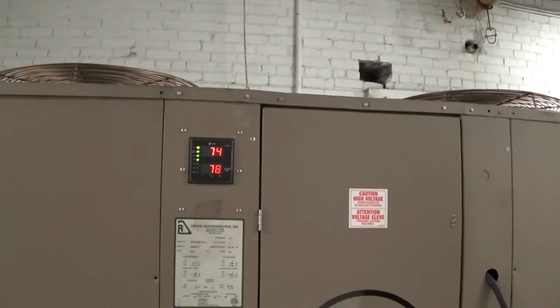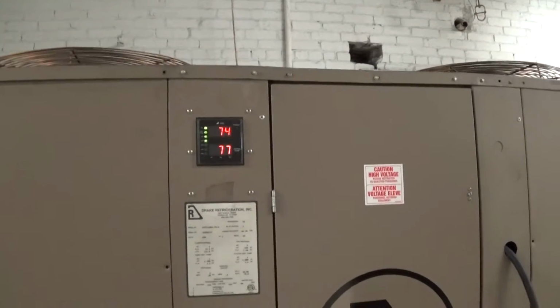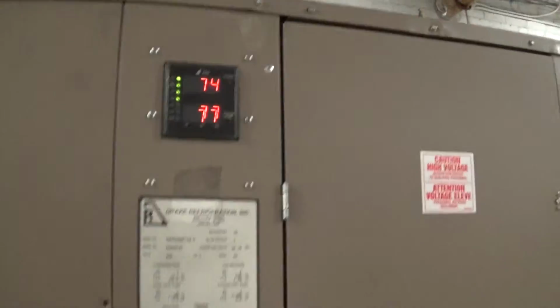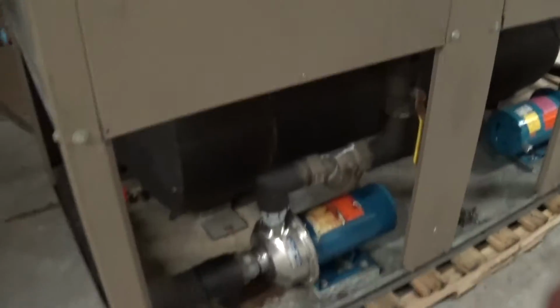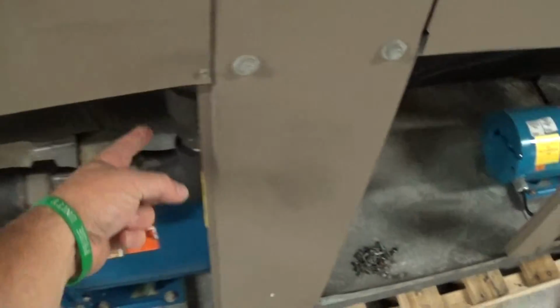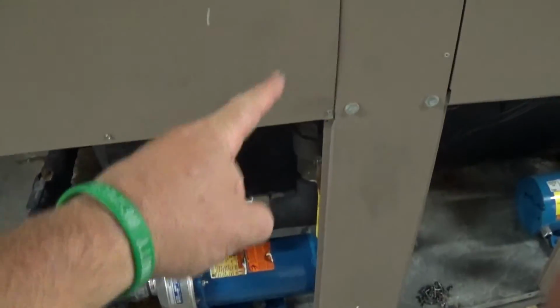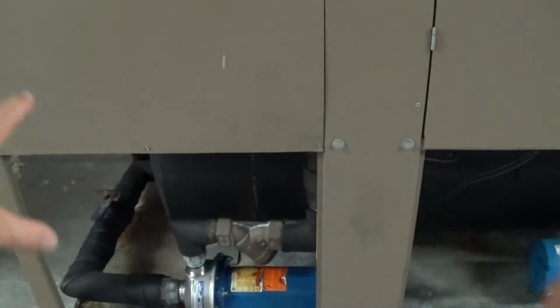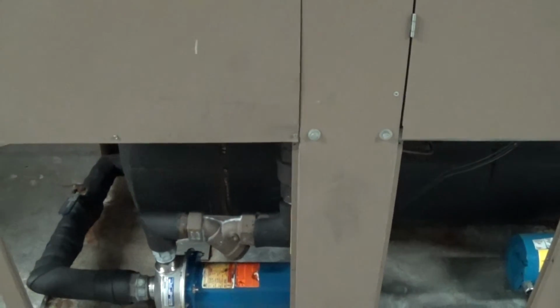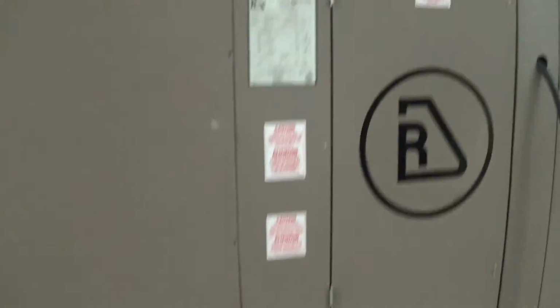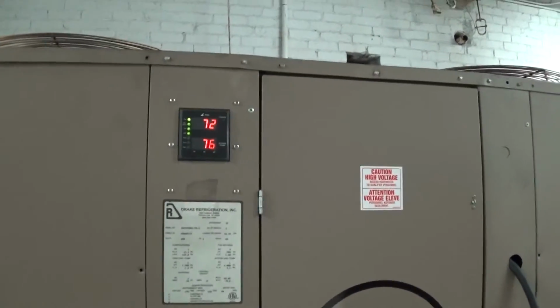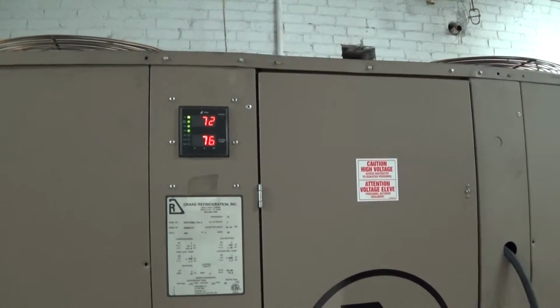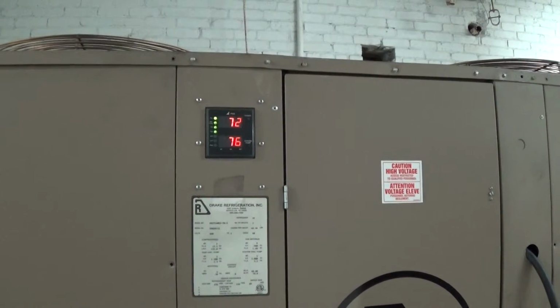So we will see a bigger difference on those two sensors for temperature actually. One of them is sensing at the inlet to the tank, right about here, and the other one is sensing just above here on the suction from the tank going to the evaporator. The tank is so big and it's getting so much circulation inside, there's going to be some differences in those two temperatures. So I'll come back to video number 2 here as we get close to the set point temperatures.